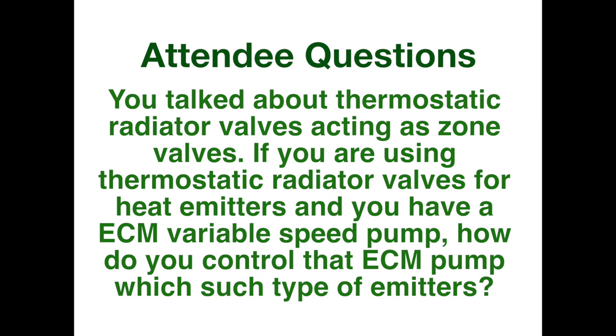Yeah. And there's a couple different ways you can do this. Probably one of the most clever that I heard is our friend Nathan White up in Alaska. He uses thermostatic radiator valves on panel radiators, and he's using a little Delta P pump. What he found is Phoenix Controls makes a little induction relay. It's a little relay that you just wire into the pump. It senses when that pump, even at a very low flow rate, wakes up or comes on, and then it just makes an end switch.